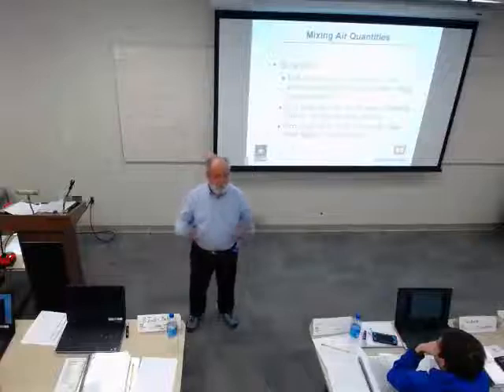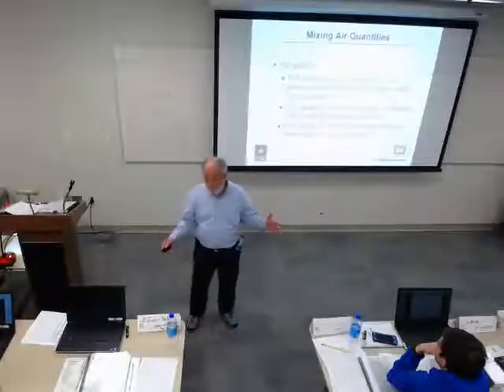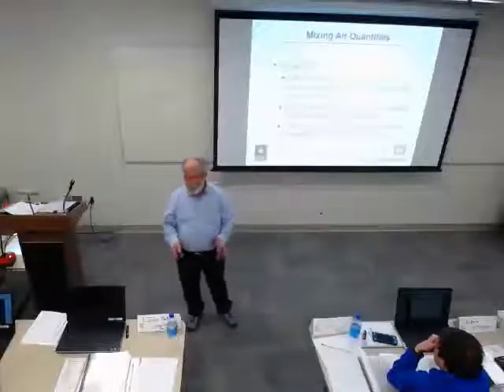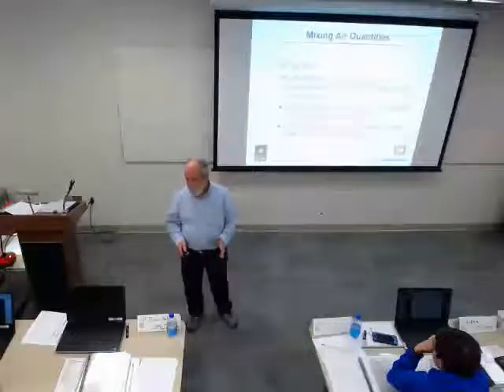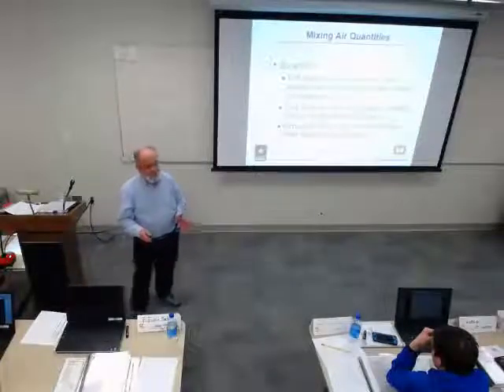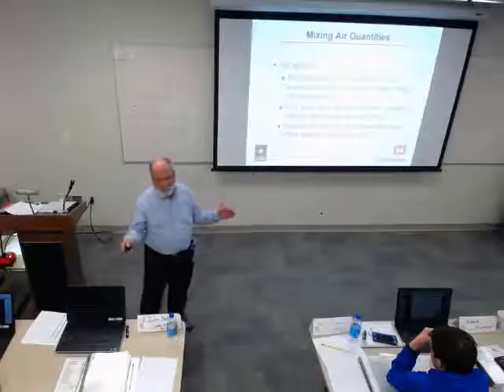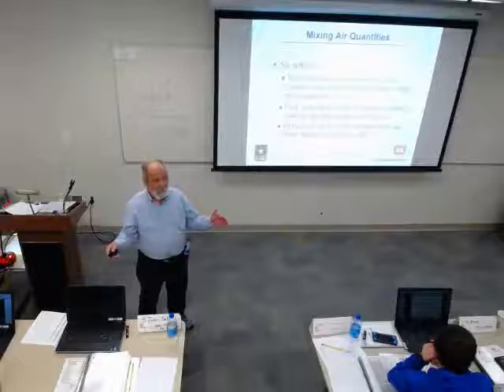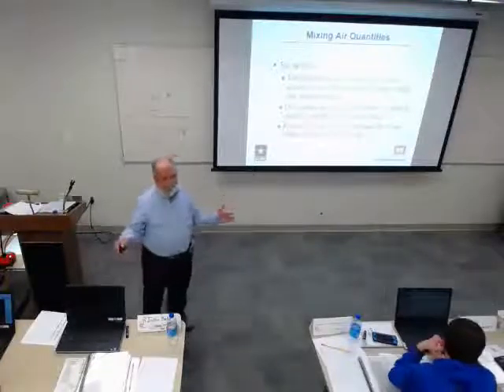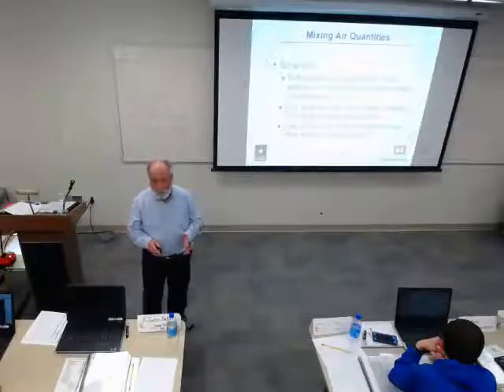Now, another thing I want to say about this: if you're going to use this, you want to be sure that the temperature difference between the return air and the outside air is large enough. Let's think about it like this. Suppose the difference is 10 degrees. If 10 degrees represents 100%, then each degree is 10%. Well, suppose instead that our difference is 20 degrees. Now each degree represents 5% of the total. You can see that a measurement error of one degree is not as serious when each degree is 5% as when it's 10%, because the percentage of your error is going to be on a smaller part.